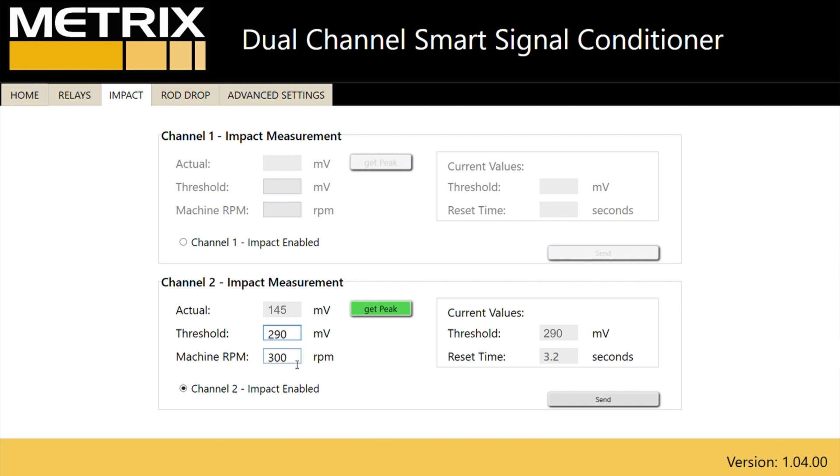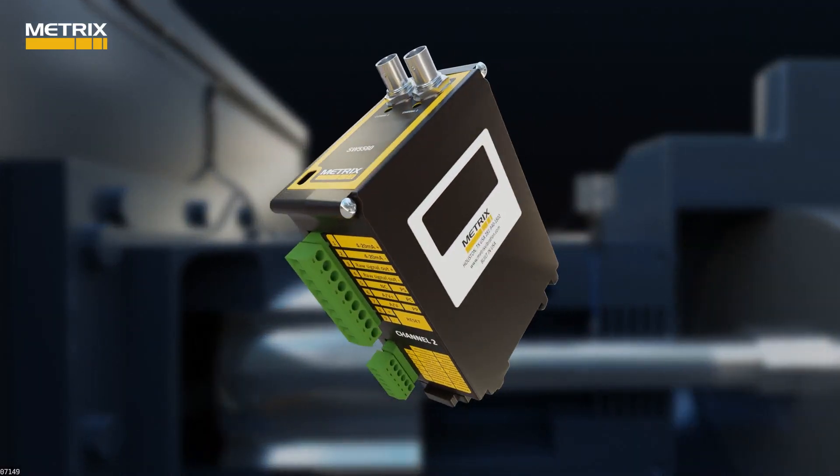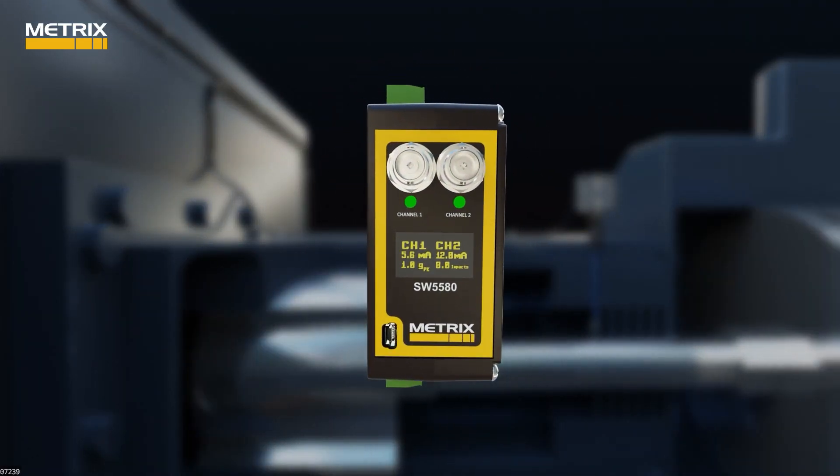Then you insert the machine speed in revolutions per minute. In this case, we will use 300 RPM. Notice the reset time is automatically set by the software to measure impacts within 16 revolutions of the machine — in this case, 3.2 seconds. After the Send button is clicked on the software, the SW5580 will start measuring impact on channel two.